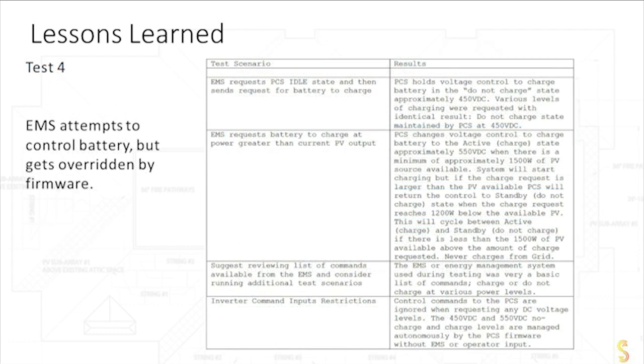And then another test that we do actually is test number 4, what we call test number 4. This is actually where we test to make sure that even if there's an EMS, an energy management system, even if there's another brain or a controller on the system, that it will always be overridden by the firmware in the inverter. This is actually one of the reasons why we call it firmware, not software. Firmware, like the name suggests, it's firm. It's built or hard-coded, if you will, into the inverter and is unadjustable. You cannot get in there and tweak it and change the rules.